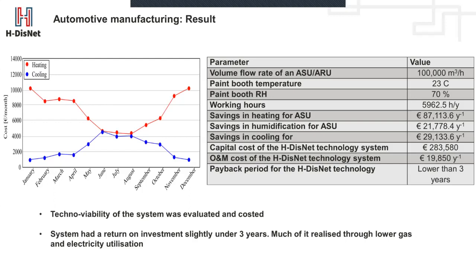Yes, you are correct. The absorber configuration is valid for both cases. Depending on the situation, the equilibrium between salt solution and air lets us heat or cool. In summer we needed in any case to remove humidity from the air, meaning in the absorber we wanted an absorption process. That process releases heat, so we had to cool down the temperature of the salt solution. But in any case, we also have evaporative cooling on the table, so the total energy we need is always lower than with a traditional system.